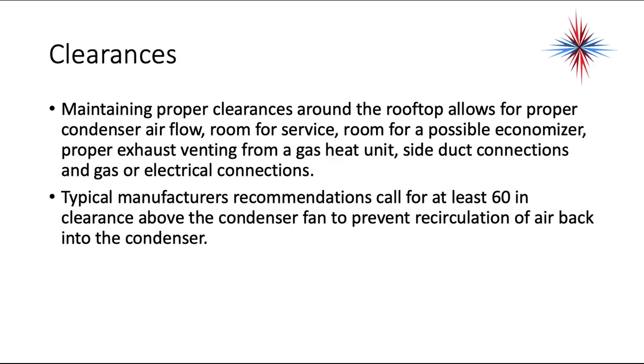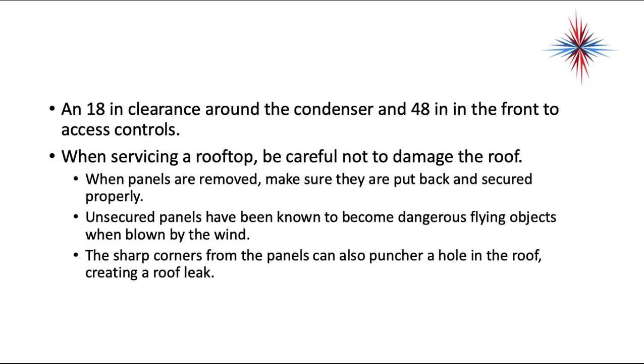Maintaining proper clearances around the rooftop allows for proper condenser airflow, room for service, and room for possible economizer, proper exhaust venting from gas heat units, side duct connections, or gas and electrical connections. Typical manufacturer recommendations call for at least 60-inch clearance above the condenser fan to prevent recirculation of air back into the condenser, 18-inch clearance around the condenser, and 48 inches in front of the access panels.